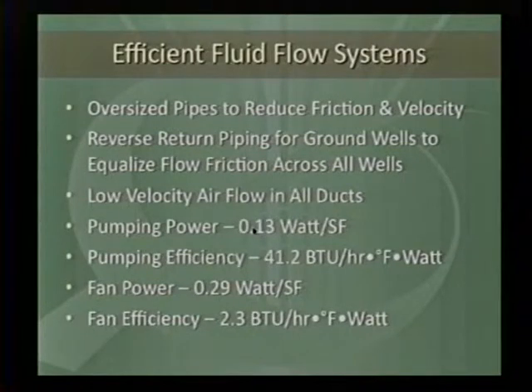Now, I already said quite a bit about efficient flow systems, but just a couple of numbers that you can use to sort of check your own designs. The pumping power on this building, and this is per gross square foot of the conditioned area. Okay, so if you're doing a fully conditioned building, gross square foot of that area. The pumping power is 0.13 watts per square foot, and the efficiency is almost 41 BTUs of heat transferred per hour per degree of temperature rise in the fluid per watt of pump power. For fan power in this building, we're at 0.29 watts per square foot, and we're able to transfer 2.3 BTUs per hour per degree Fahrenheit of temperature rise in the air per watt.